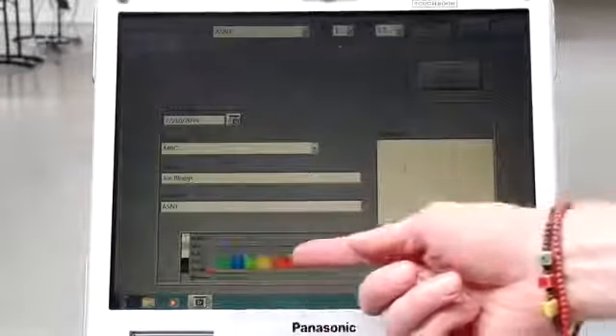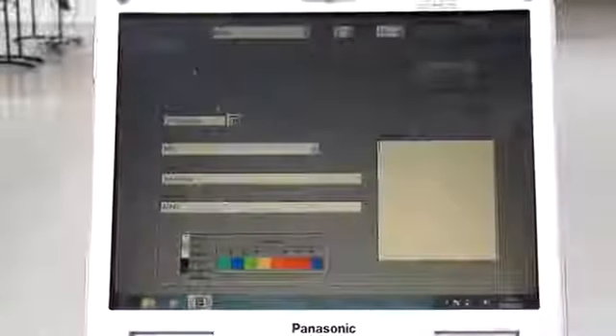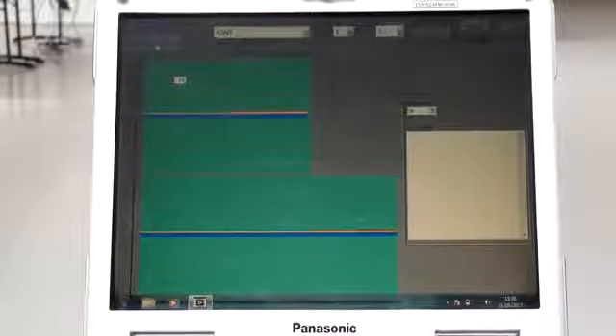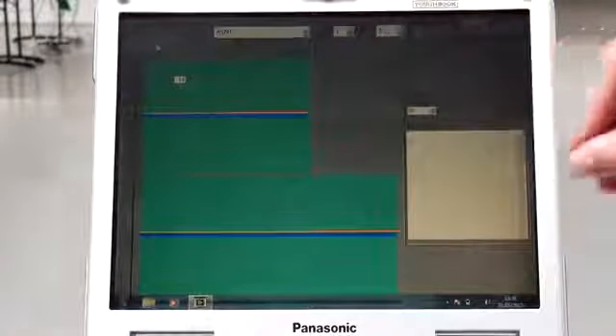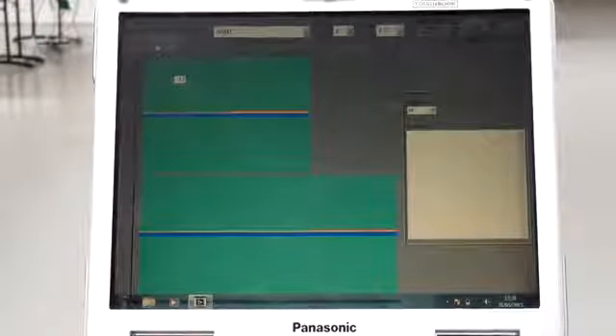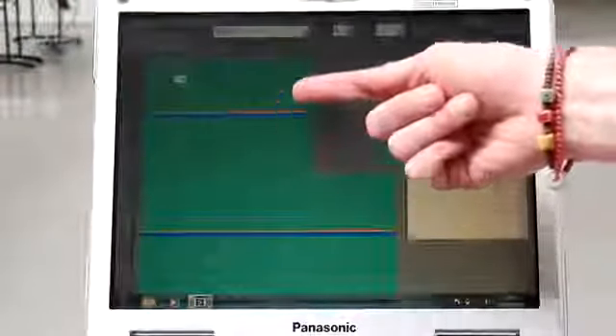A colour map, which is used to display colours in the C-scan corresponding to different through-wall thicknesses, is displayed here. This can be edited as required. The tank tab shows a top-down topographical view of the tank that is being inspected. This dynamically changes as more plates are scanned and incorporated into the inspection data. The colour bars on each plate show the percentage of the surface area of the plate of that depth.